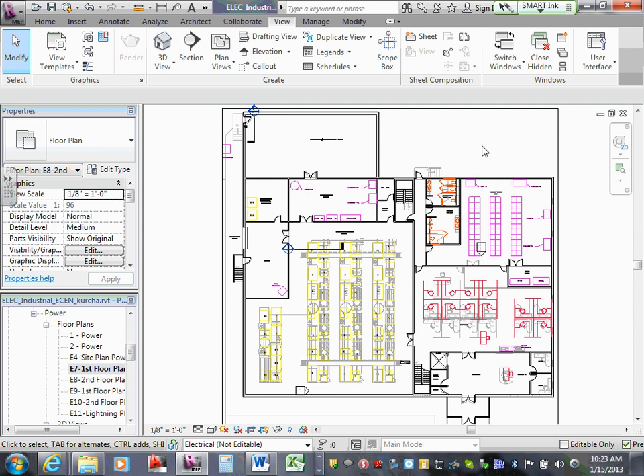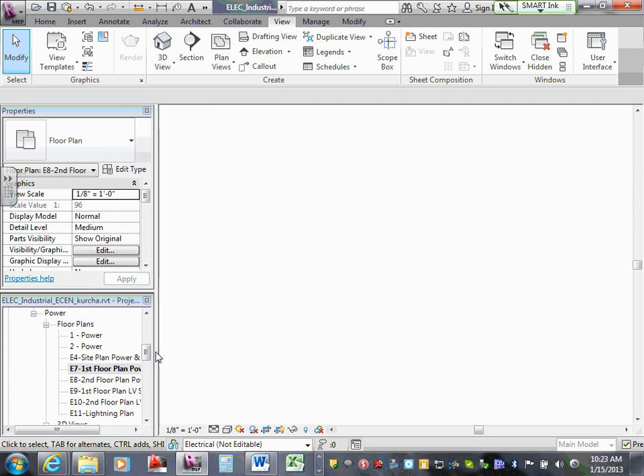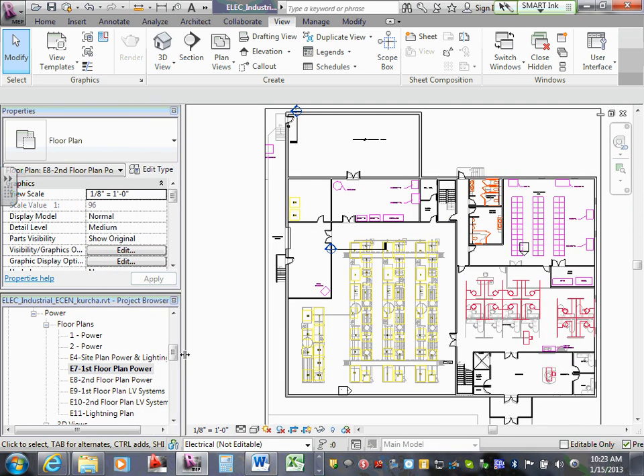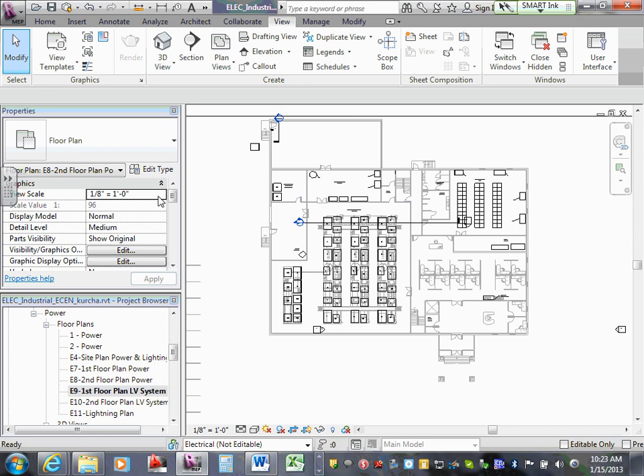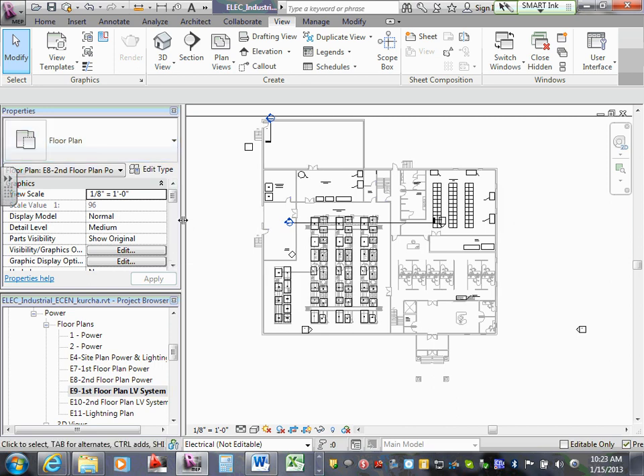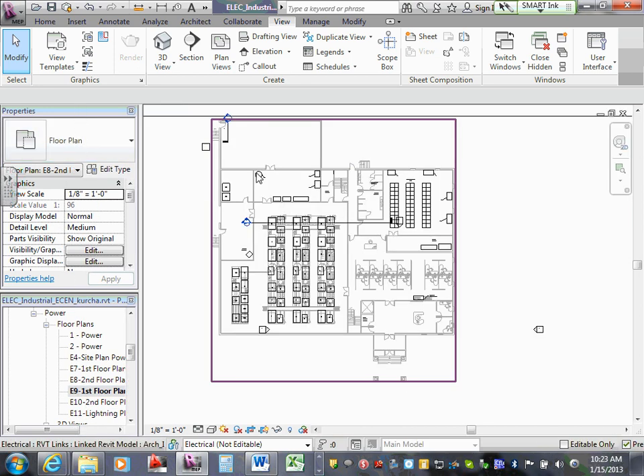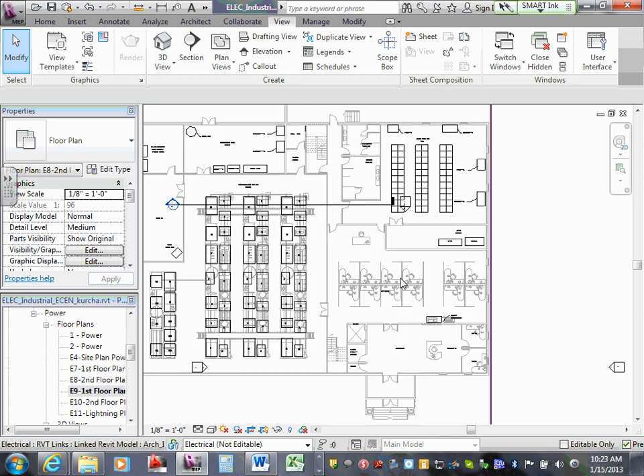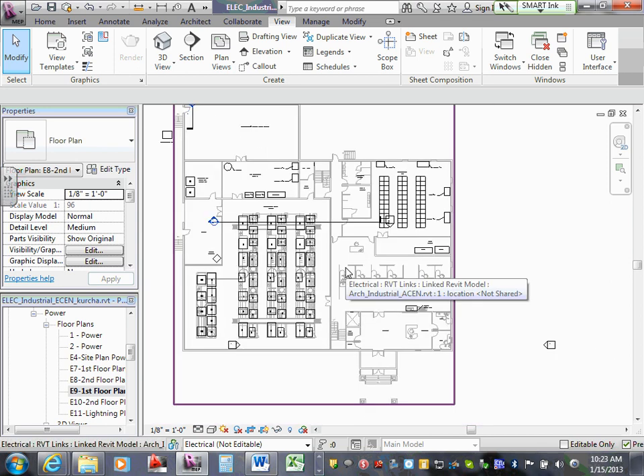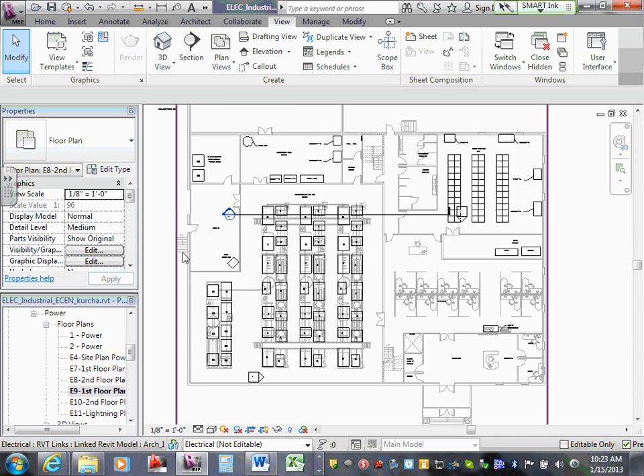So it's all dependent on what the code is going to require and how many devices you are allowed. Typically, in the specifications, the engineers will tell you you can only put 80% of detect devices on a single loop. So it's designed that way, but in fire alarm systems, the new ones that are coming out, it's all computer based now. You're not looking at hard chips, you're not looking at burn-in boards, so you can easily upgrade the fire alarm system.